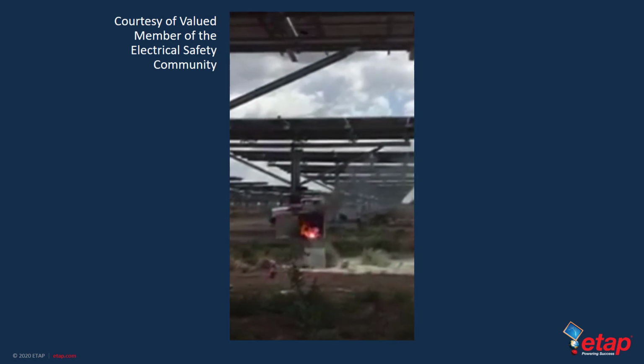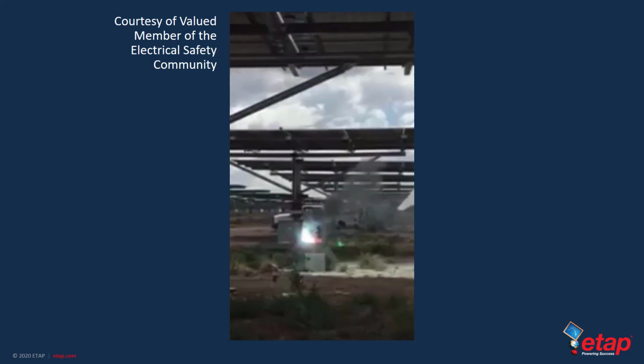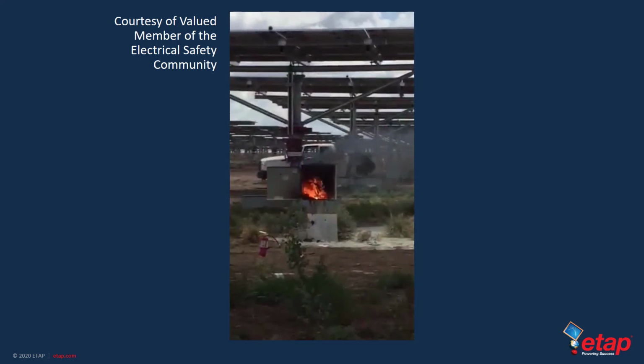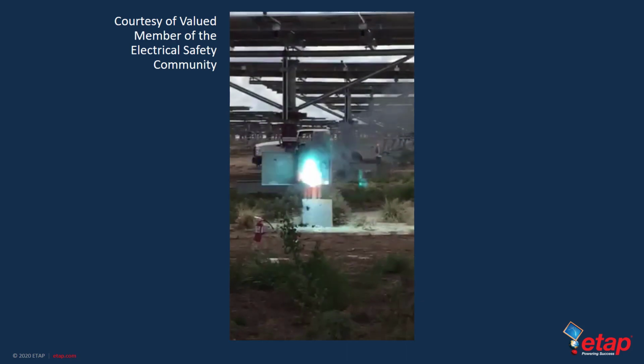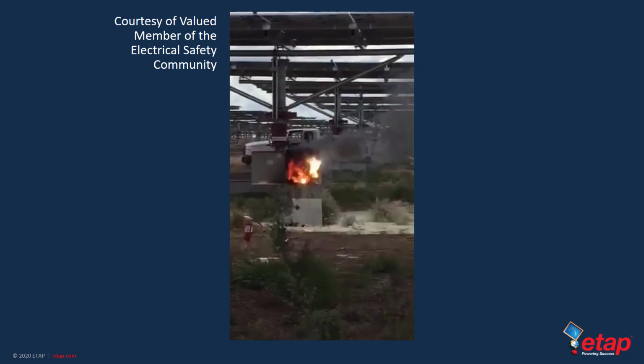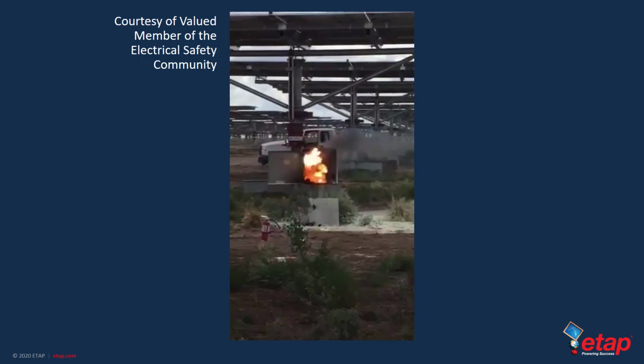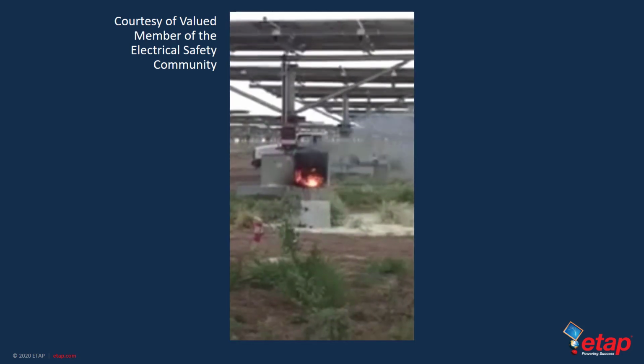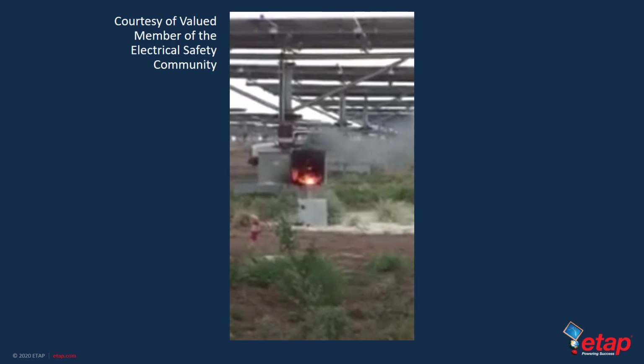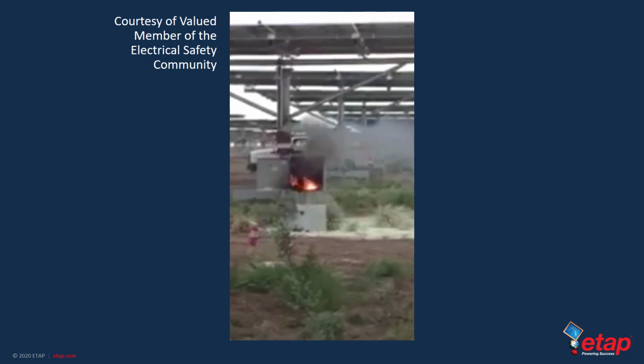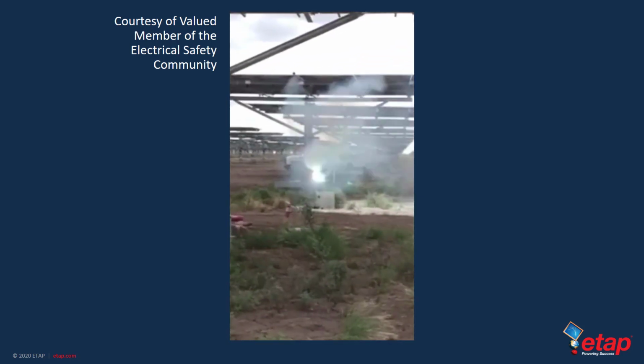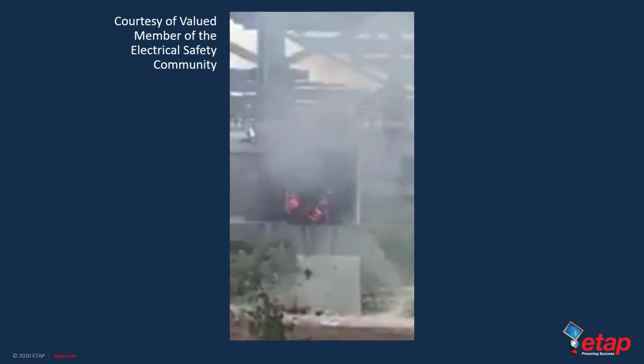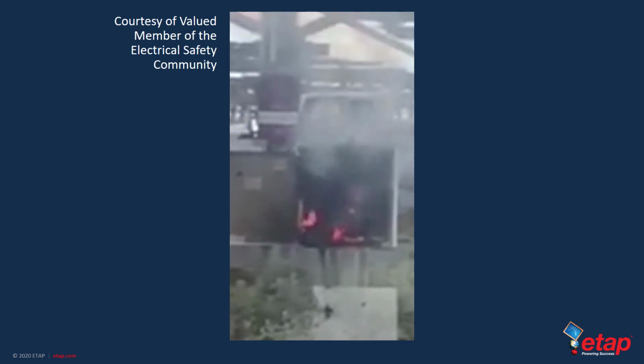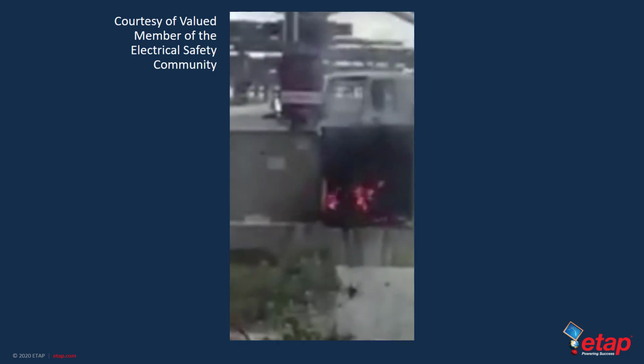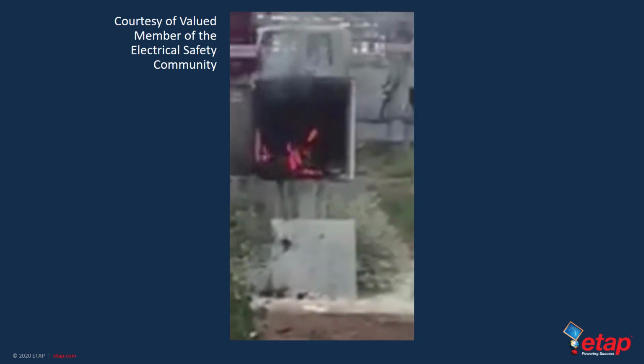Similarly, we can see that the photovoltaic system is a significant fire hazard, and thus DC arc fault detecting relays and equipment has been now mandated by code requirements by the NEC for certain rooftop installations where this could cause a fire. Note that at least for this fault, it does not seem that the energy produced is actually a significant ionization of the material and ionization of the air materials around the arc. There doesn't seem to be a significant size plasma cloud or molecular cloud generated.